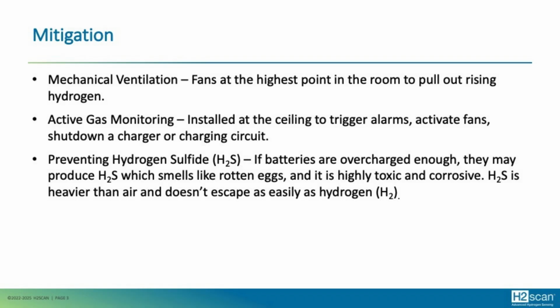So you can have multiple phases for the different levels of hydrogen, working within that 4-to-1 safety margin. We also want to prevent building hydrogen sulfide. Hydrogen is lighter than air, and this is the first gassing that happens out of a battery. But if a battery continues to be overcharged, it could produce hydrogen sulfide. This is where you have two hydrogen atoms binding with one sulfur atom. Because of that composition, it is heavier than air and sits mostly towards the floor, and it's a heavier gas.